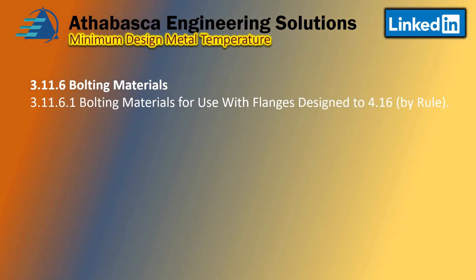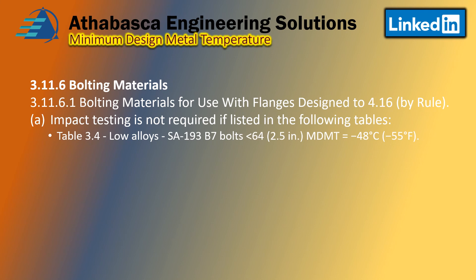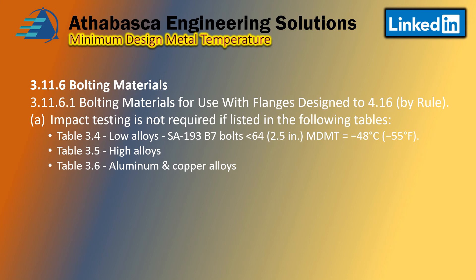For bolting materials — used with flanges designed per 4-16 — Part 4 of Section 8, Division 2 is design by rules and Part 5 is design by analysis. Impact testing is not required if listed in the following tables. Table 3.4 for low alloy bolts: a common one is SA-193 B7. If your bolt size is less than 2.5 inches, the MDMT listing is minus 48°C. High alloy bolting materials are in Table 3-5. Table 3-6 covers aluminum and copper alloys, and Table 3-7 covers nickel and nickel alloys.